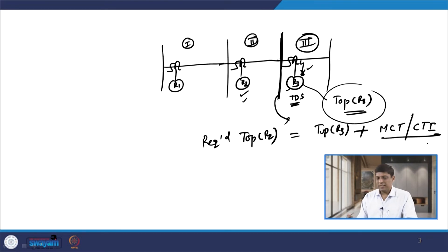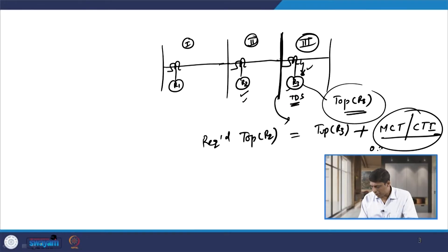This MCT depends on many parameters — for example, the errors in the CT, the errors in the relay, plus some safety margin. Based on all of that, the minimum coordination time interval can be considered in the range of 0.2 to 0.3 second. In this case, we need to add either 0.2 second or 0.3 second, or any value in between, and then decide the time of operation of relay R2.